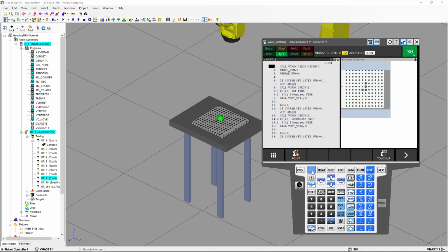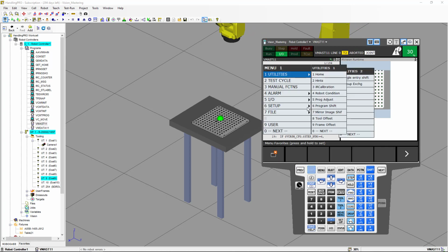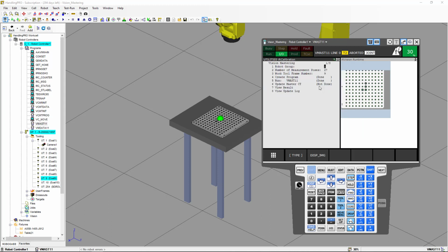Now the program is finished. We need to go back to menu, utilities, iRCalibration, and select update master counts. Press select, then shift update. You'll see the compensation angle here - in your case, in the real world, you'll have different values. We have here just J3, that's 0.01.